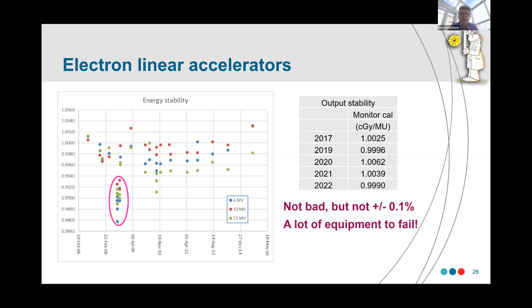And there's a lot of equipment in an electron linear accelerator that can fail. And this is the report from the AAPM Task Group 142 on quality assurance. I don't want to discuss any of this, except to say that this was the annual QA, and this is what's required just to get 1 to 2% constancy. So if we're talking NMI level, can we get to 0.1, 0.5% maybe, it gives you an idea of how much QA you need to put into place and maintenance to ensure that you've got this reference field from a linear accelerator. For a cobalt-60 irradiator in comparison, our QA is we check the field size, we check the SSD, and we verify that the source comes out to the right place, and that's it. The difference is very stark.